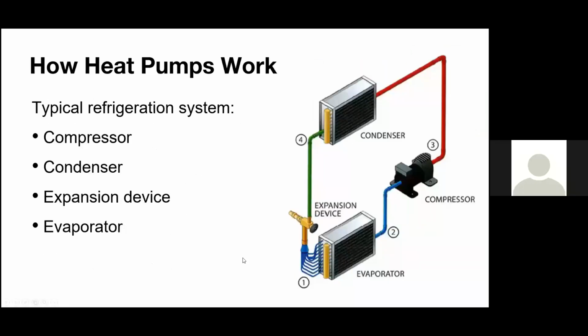So jumping into the components of any refrigeration cycle. You've got these 4 components. The numbers here represent the actual refrigeration lines, but looking at the components, we have the condenser, compressor, evaporator, and the expansion device. So number 2 is the refrigerant suction line going into the compressor. Number 3 is a discharge line or the hot gas line that is going outside to your condenser. Number 4 is your liquid line going from your condenser back to your expansion device. And then number 1 is what we call the coil distributor.